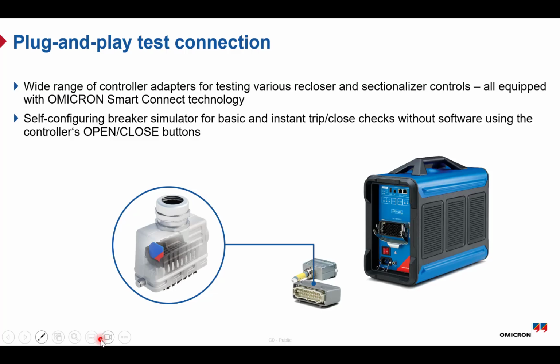Another useful feature is the built-in breaker simulator. With this, you can perform a quick trip and close checks directly from the controller even without using the software. So you can verify basic functionality instantly, just using the open and close buttons.